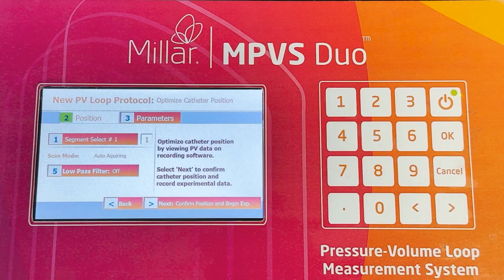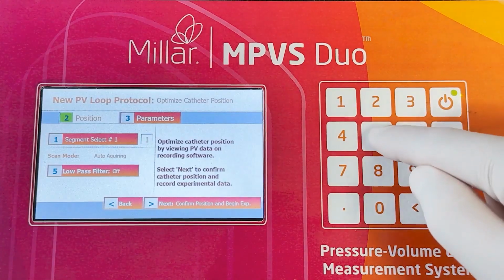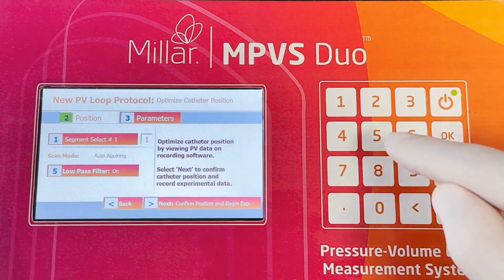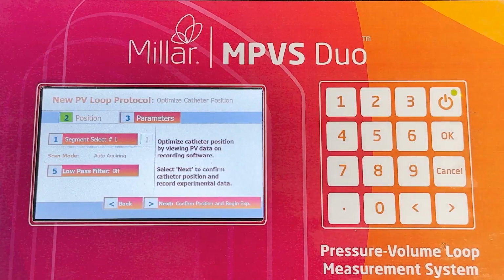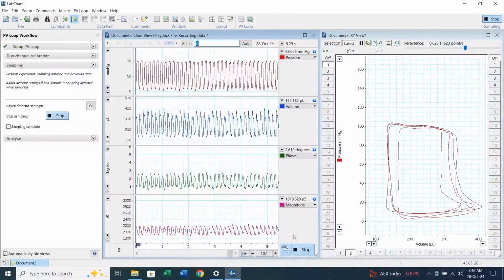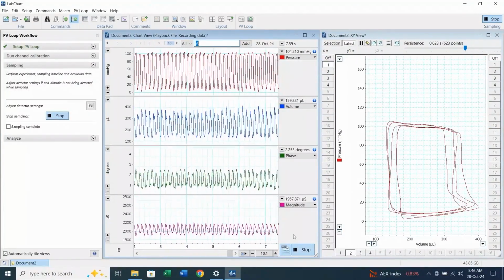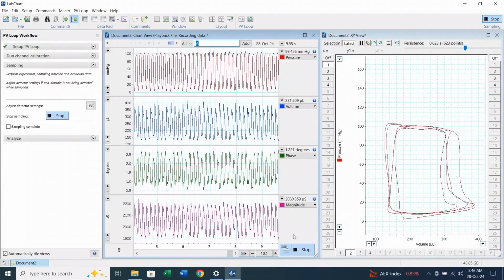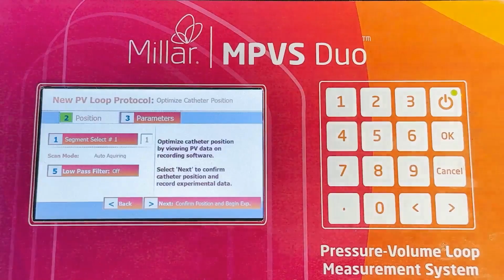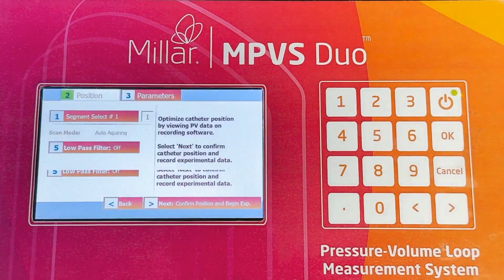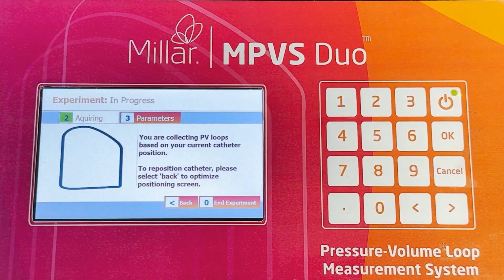A low-pass filter can also be switched on in this screen by pressing 5. Once the catheter position is optimal, with phase and magnitude being within the specified range as shown in the manual, the forward arrow button on the Duo can be pressed to move into experimental mode. Once in experimental mode, the experiment protocol can be followed to record baseline and occlusion data to calculate load-independent parameters such as ESPVR and EDPVR.